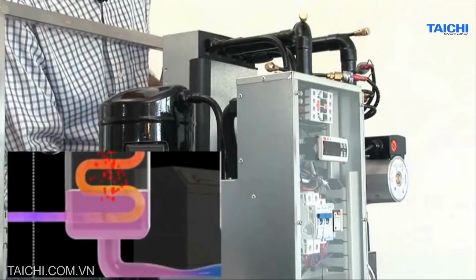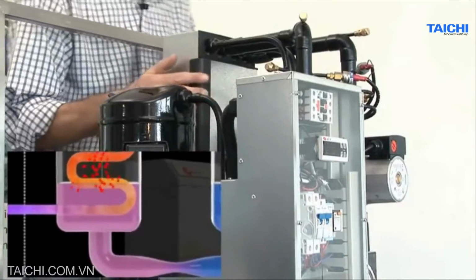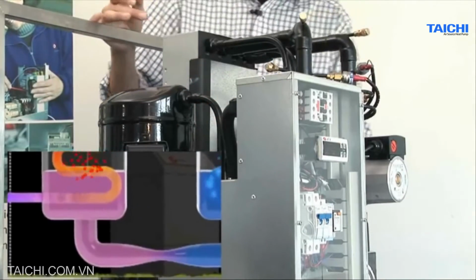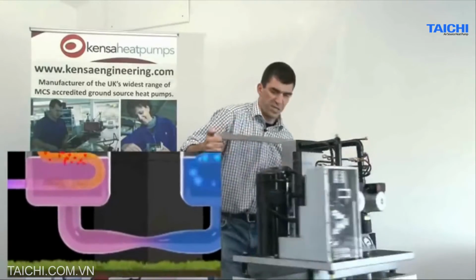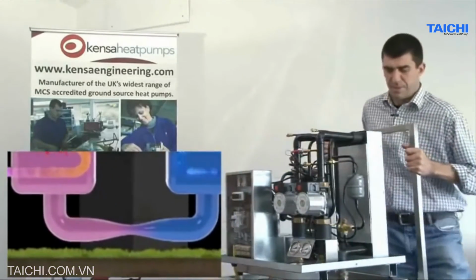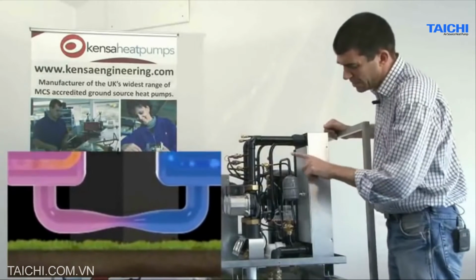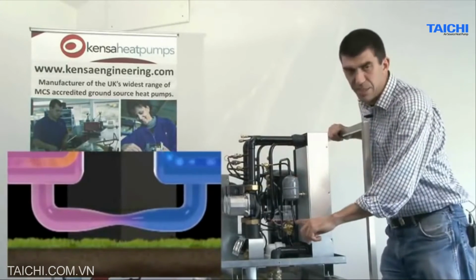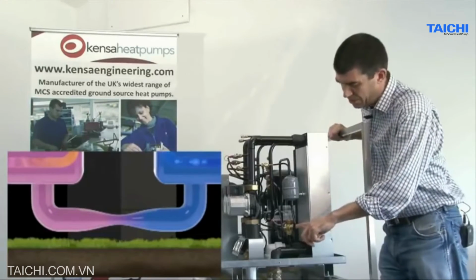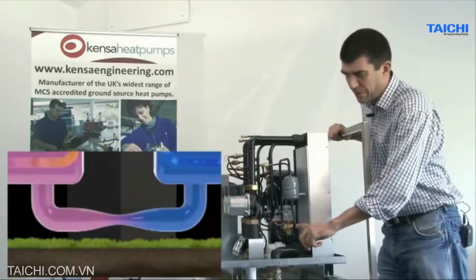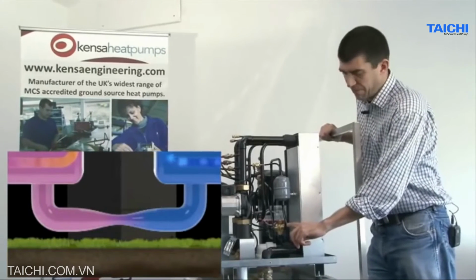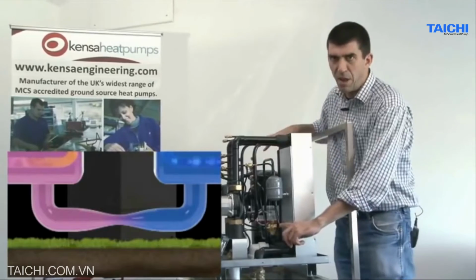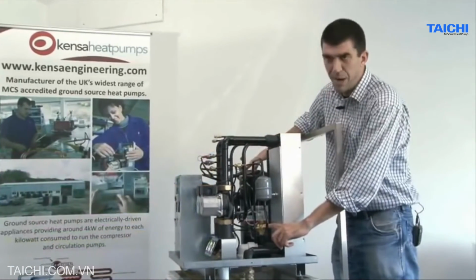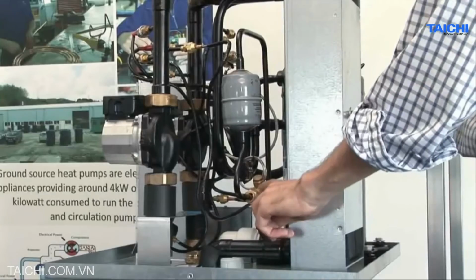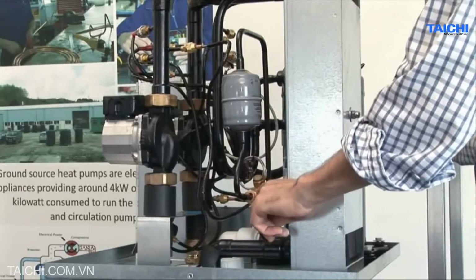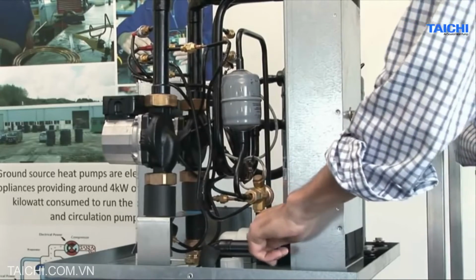With the pumped action, the liquefied gas rises up the pipe, passes through the filter, which keeps it nice and clean. I'm going to turn this around. Passes through the filter, and it meets the restriction, which is the expansion valve. What the expansion valve does is it creates a little fight. It's holding back the flow of refrigerant that the compressor's trying to push through. That means that after the liquid passes through the expansion valve, it drops in pressure.